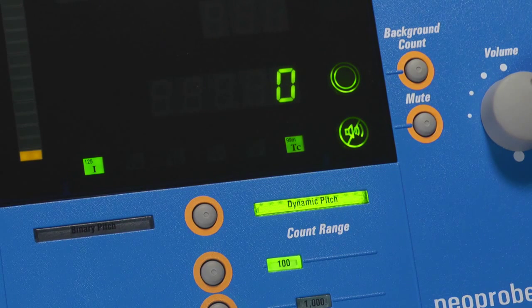Lastly, if an open window is desired, this can be achieved by pressing and holding the radionuclide button, thus removing the upper and lower windows and allowing the probe to capture all ambient gamma radiation.